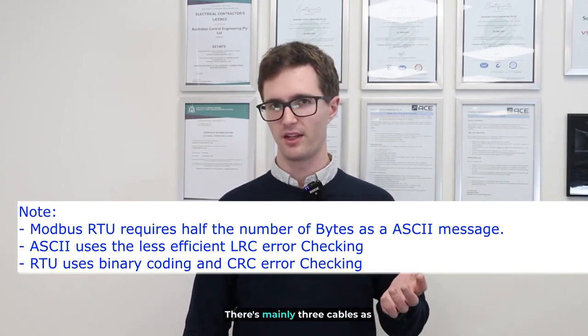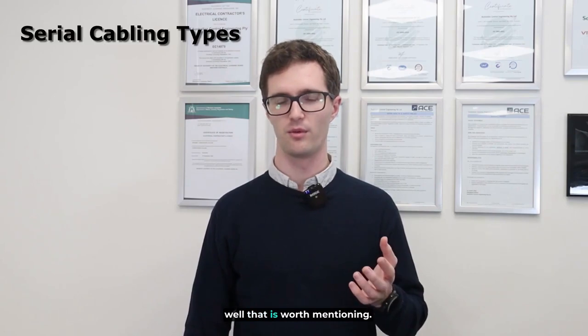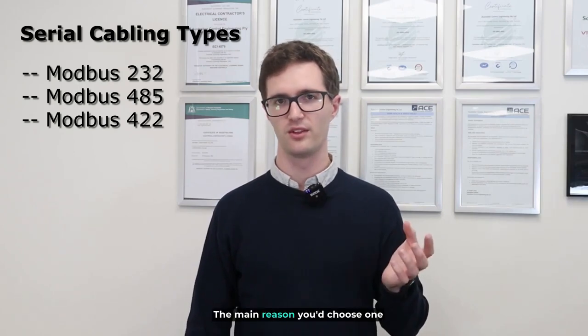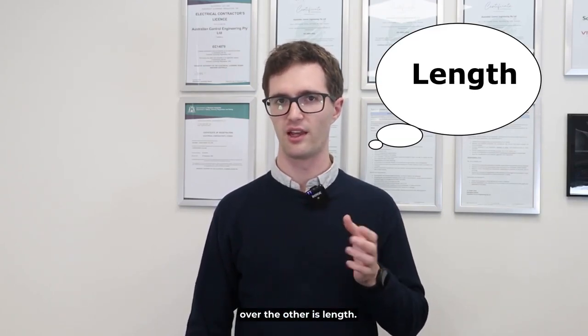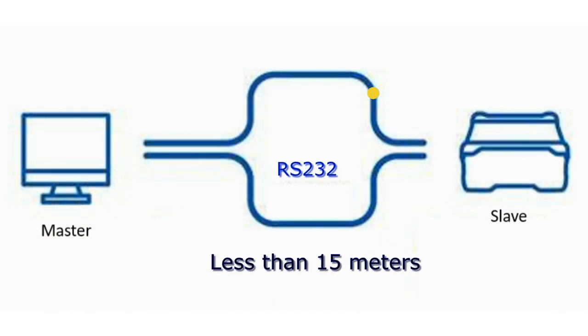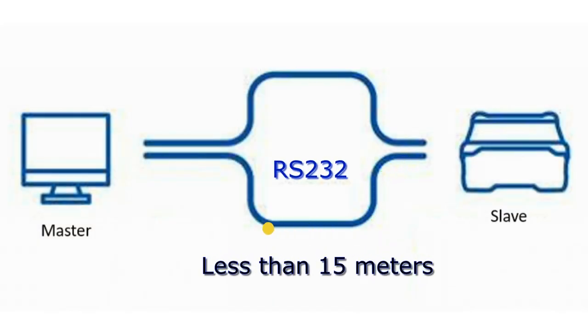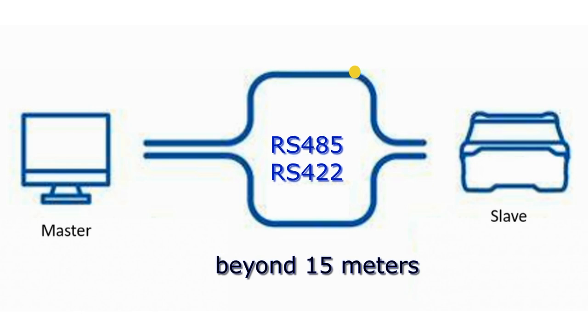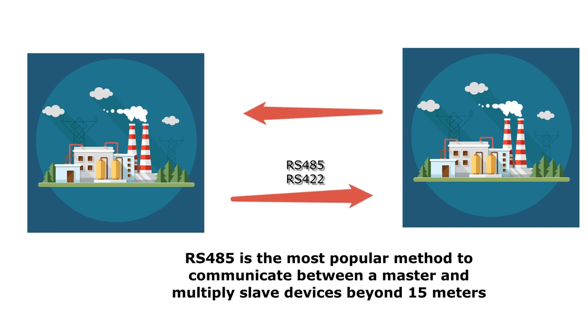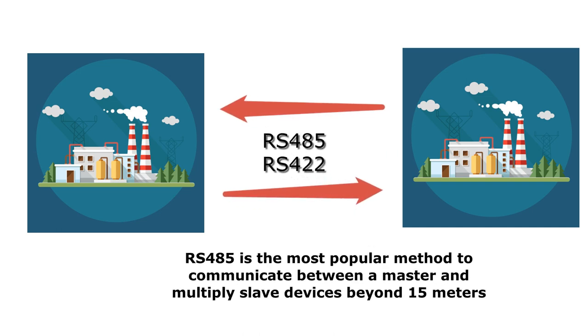There are mainly three cable types worth mentioning: Modbus 232, 485, and 422. The main reason you'd choose one over the other is length. Modbus 232 is mainly used for short communication, perhaps under 15 meters or so. 485 is used for longer wire lengths, so if you need to send data across a site beyond 15 meters, it's a wiser choice to use that type of cable.